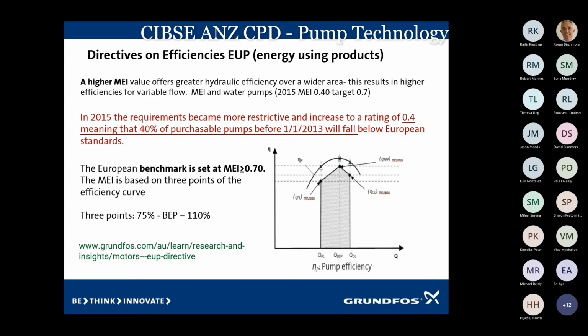What it did was take that efficiency, the shape of that efficiency, it's still holding the same peak, but it broadens the peak. So now we've got a pump that can work under variable loads and still maintain a nice efficiency. Whereas if you take an efficiency like the grayed out one, which is very peaky, it's all very well to have your pump running at that efficiency, but as soon as you drop the flow rate 20, 30%, you've just run out of your peak efficiency, and now it's costing you money to run that pump. So in doing this, it's reduced the energy, and the pump's going to run a lot smoother. The target is 0.7. So the MEI target is 0.7, and most manufacturers now will meet 0.7. So for the customer, it's a real bonus. It's a real benefit. That pump is going to be running a lot smoother. It's less service and a lot more efficient over a broader period.